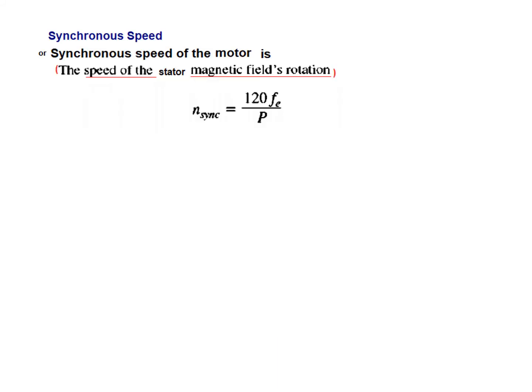During our discussion we come across the term synchronous speed, also called the synchronous speed of the motor. This is primarily the speed of the stator magnetic field rotation. It is denoted as N_sync and given by the formula: N_sync = 120 × f_E / P, where f_E is the frequency of the supply voltage to the stator and P is the number of poles.